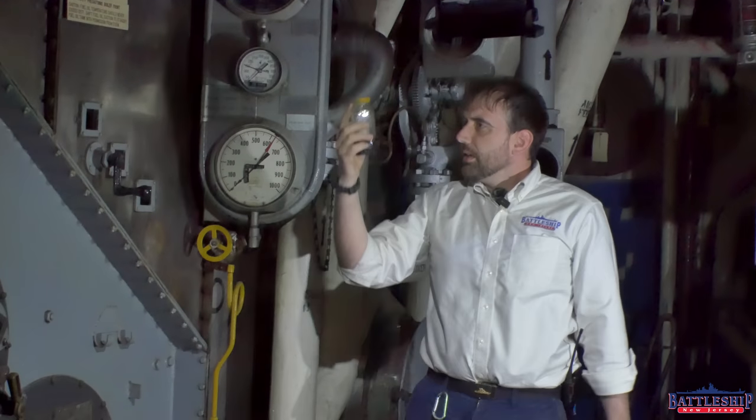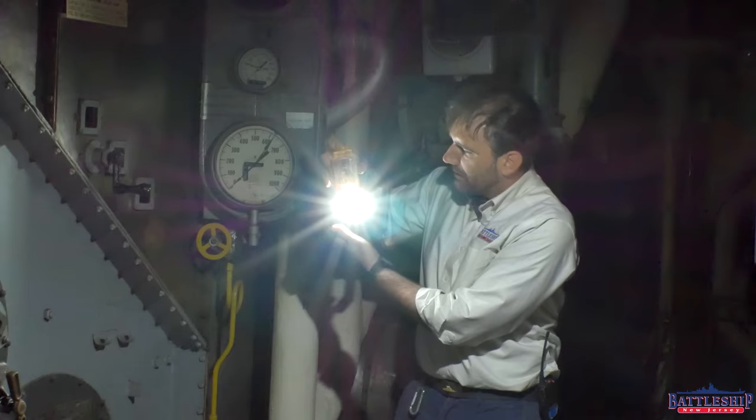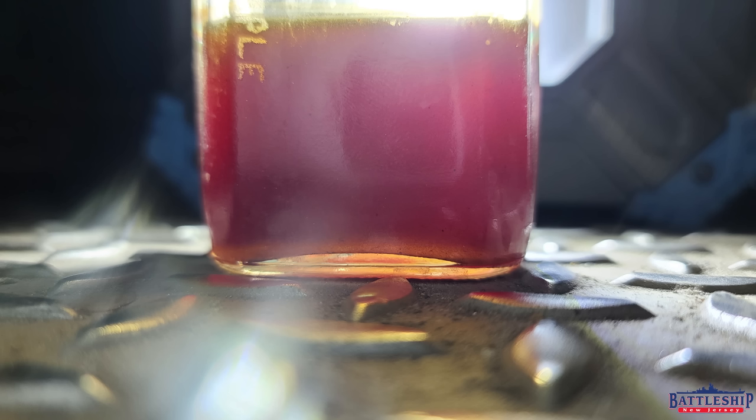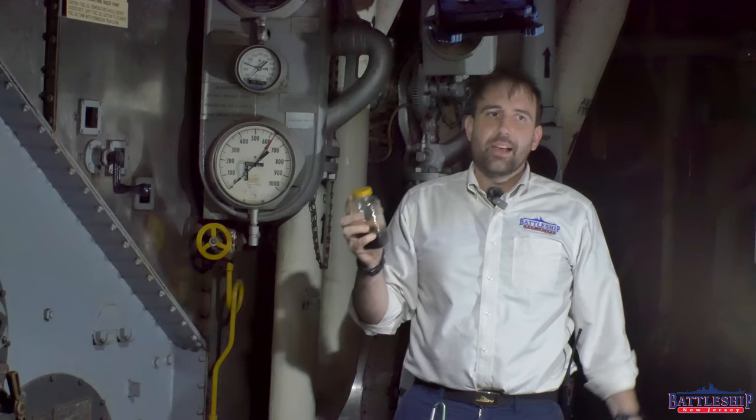So I've got this dark fuel here. Is this still good to burn? Notice when I put the light behind it, I can now look in and see if there's any particulate in there, there is not, although it has gotten cloudy from sitting there for a while. But that's how you would check the various fuels, lubricating oils, and other things in here. Now, you wouldn't necessarily be doing it by hand, come over here with me.